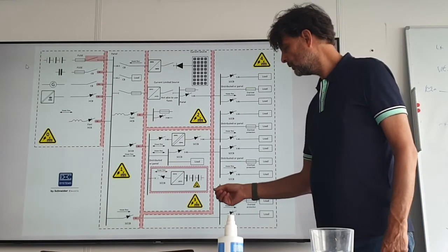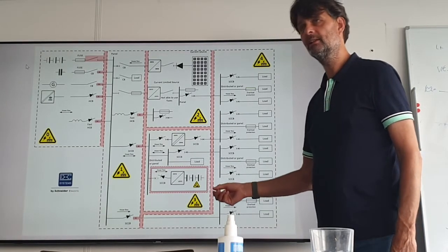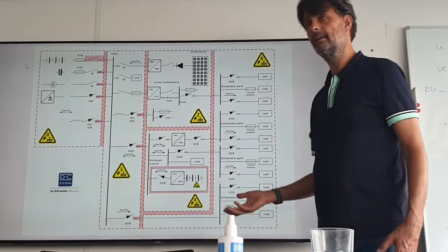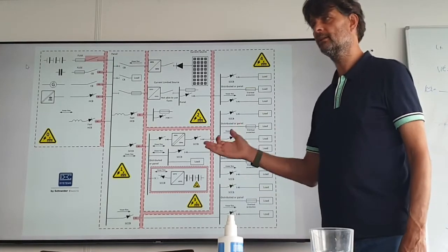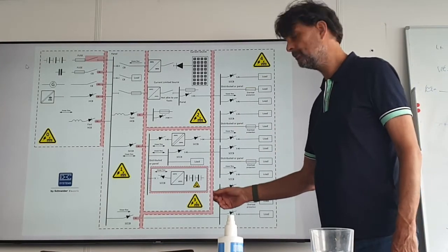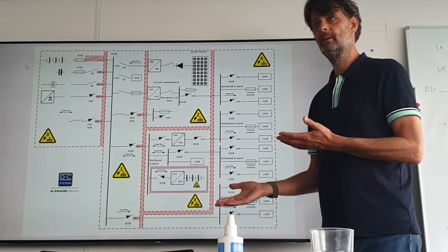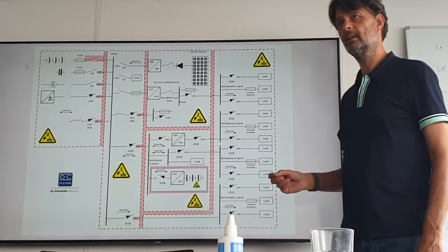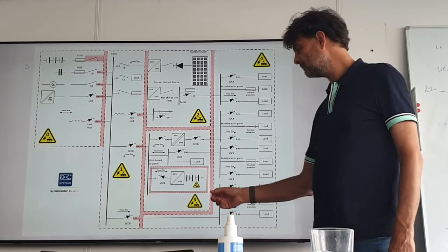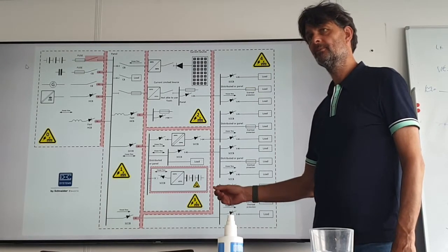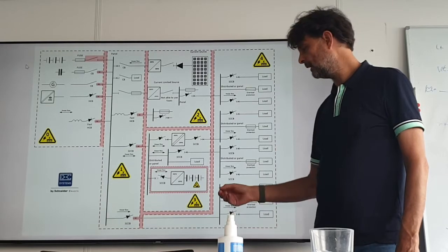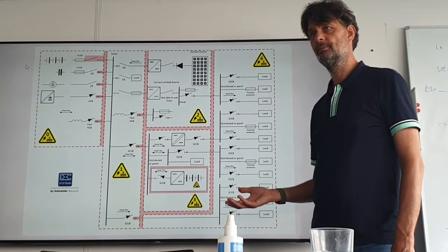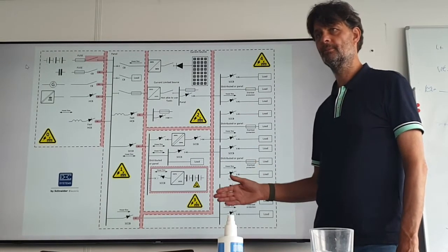So we could use, for example, 2.5 milliseconds, 3 milliseconds, or 4 milliseconds disconnecting time, in a few milliseconds, to disconnect on different curves. And if it's 20 milliamps, 30 milliamps, you can put every level you want. In this zone we have still specified at the moment, and that will probably be changed now by the IEC, but we specified 2.5 milliseconds disconnect, and we allow up to 0.1 second if the current is below 30 milliamps. And after that we disconnect.